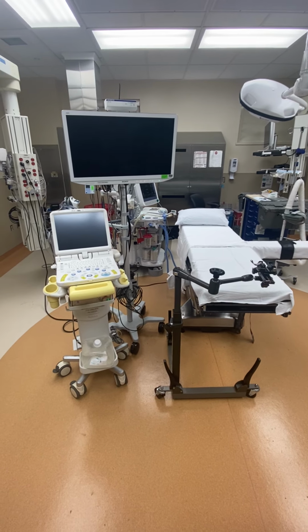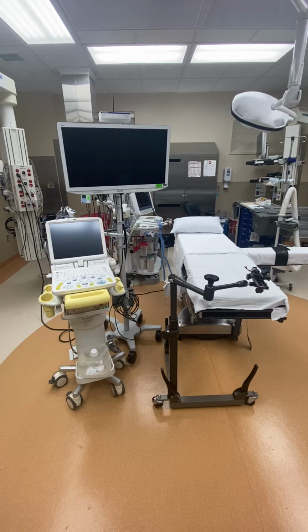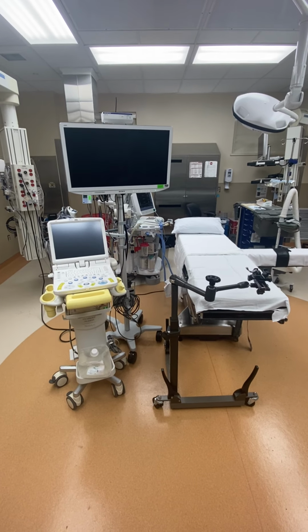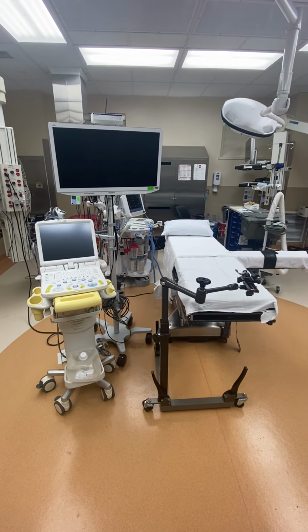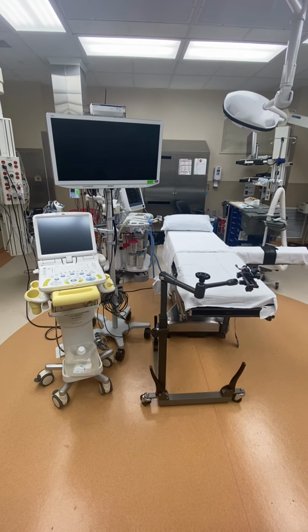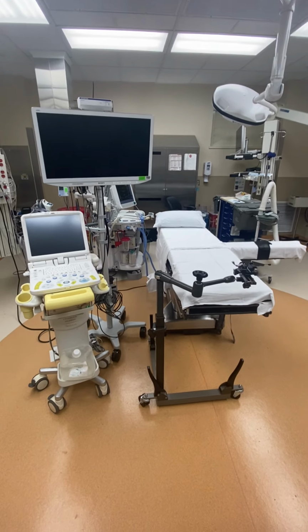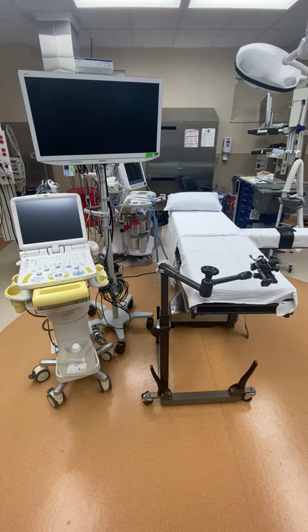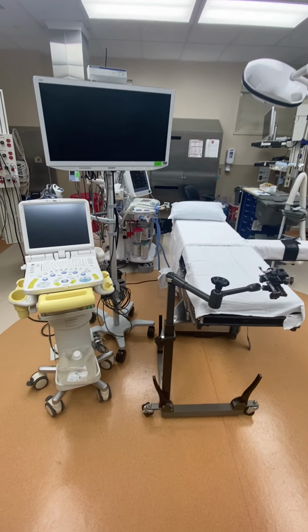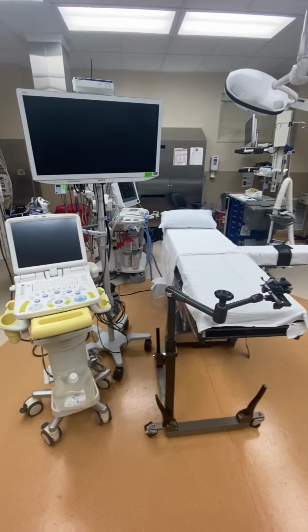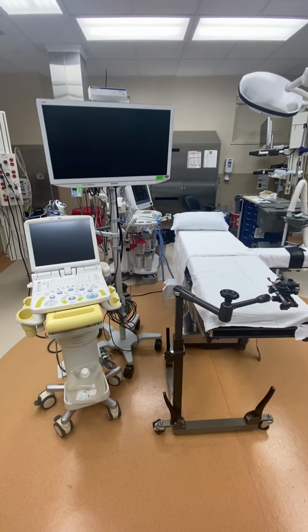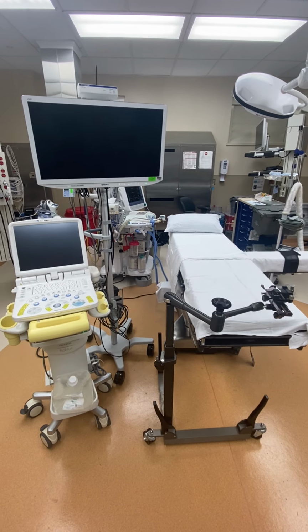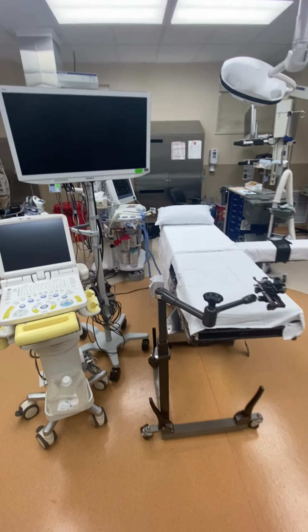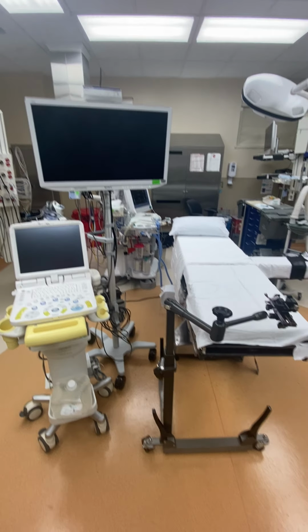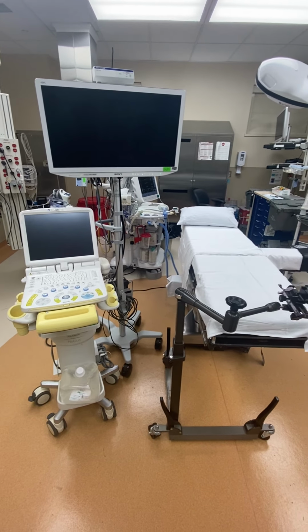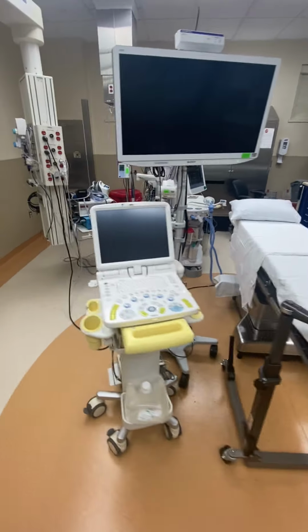Hey guys, this is a quick setup video for SpaceOAR and fiducial marker cases using the stepper stabilizer to hold the probe instead of the Artemis. As you can see, the equipment we have for these cases is the stepper, which is here on the right, the ultrasound system, and if possible, it's great to have a rolling monitor. Most of the time, the facilities have this available. We want to make sure that the monitor has a DVI input or plug. That way we can feed the DVI cable from the ultrasound to the monitor.